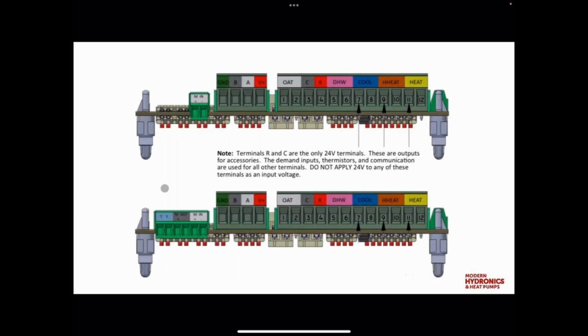And so the TT can be used in multiple different ways. Some boilers require a dry contact or a 24-volt signal for a boiler enable, and then use a 0 to 10 or a 2 to 10 VDC signal to modulate the boiler. Some boilers only require the modulating signal. So we have both options available. On this dual fuel board, we are actually controlling the boiler to assist the heat pump, whether it be for space heating or for domestic hot water needs. You can set those up differently in the screen.